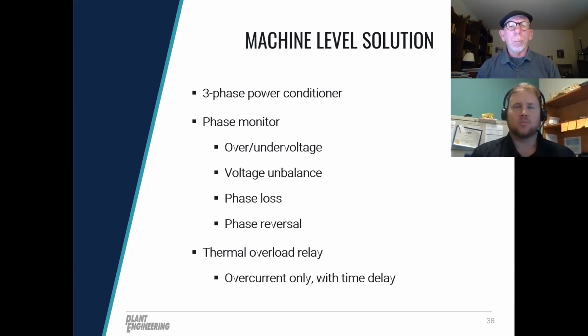Some people don't like overload relays because of the nuisance tripping. Well, if you want to avoid nuisance tripping, they do have a time delay switch. Set the timer so short-term overloads don't trip the circuit, especially on inrush when you're turning on, maybe starting up the process, turning on the motor. And then there are also varying classes of these relays that are going to trip faster than others. If you do go with this relay option, make sure you get the class that fits your application.